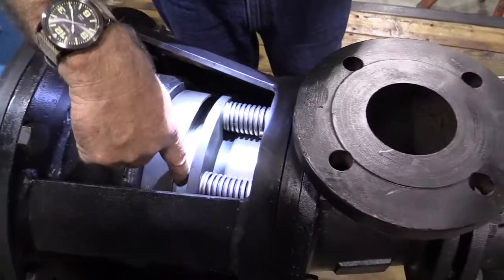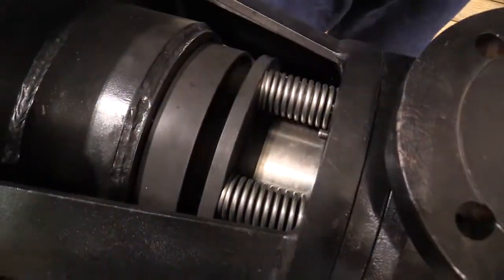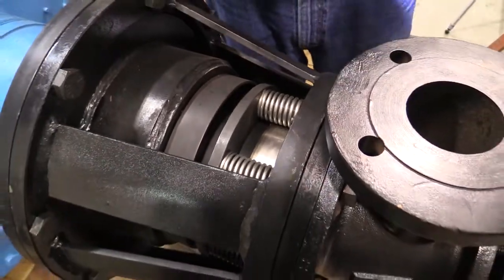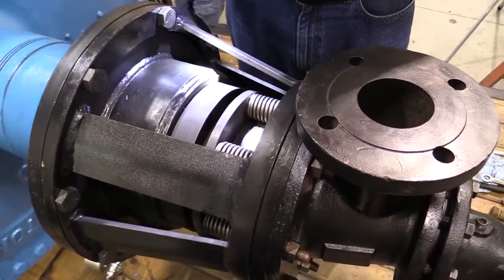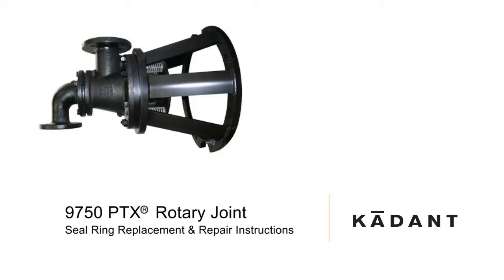Step 6. Check the seal ring alignment and the X-dimension. The seal ring should be centered on the nipple. Consult the rotary joint drawing for the correct X-dimension. Step 7. Install the inlet and outlet flex hoses using new gaskets. This completes the disassembly and repair of a Type PTX rotary steam joint. Please consult Kadant Johnson if you have any questions.